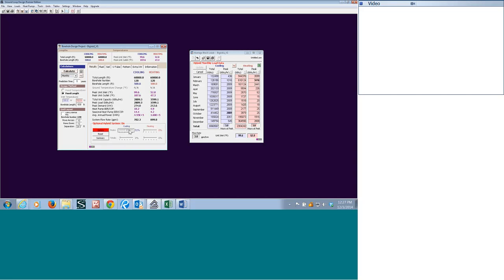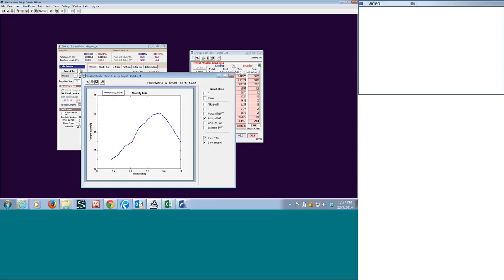But what we're going to do down here is we're going to take this up to 60% now. Now that's down to 2247 as a peak load to the ground loop. But now we're almost to 24%, almost 25% per year of shaving off the total heat rejection to the ground loop annually. So let's recalculate and see where we're at. Now that's getting a little more acceptable. Now that's at 5 years. So let's go to 1 year. Now 86 degrees, that would probably work pretty well.